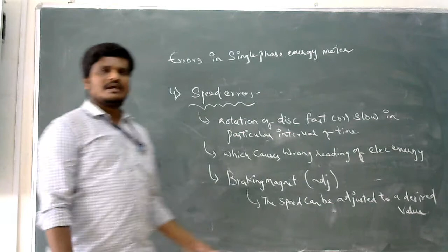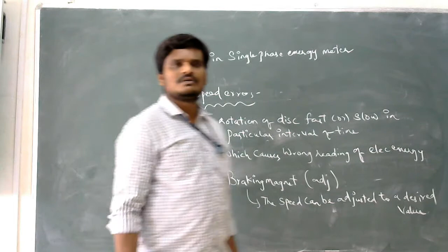So in order to reduce or compensate the speed error in case of a single phase energy meter, I need to use braking magnets which are adjustable. The main purpose of having a braking magnet is that I can adjust the speed of the disc to a desired value, in order to record the readings of electrical energy. Now we will move to the next type of error, that is errors due to voltage variations.